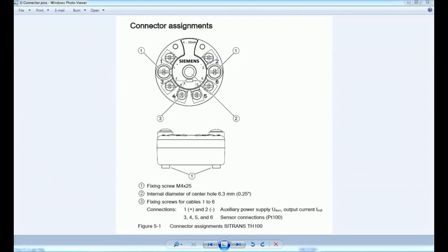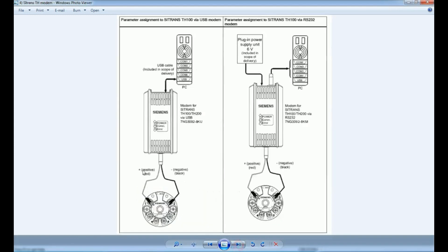Now we will see the connections on this temperature transmitter. Terminal 1 and 2 are connected with the auxiliary power supply, and from these terminals we will get the 4 to 20 milliampere current loop — that will be your signal. With terminals 3, 4, 5, and 6 we will connect the sensor, either RTD or thermocouple. Based on the application, we can connect a 2-wire, 3-wire, or 4-wire temperature sensor.